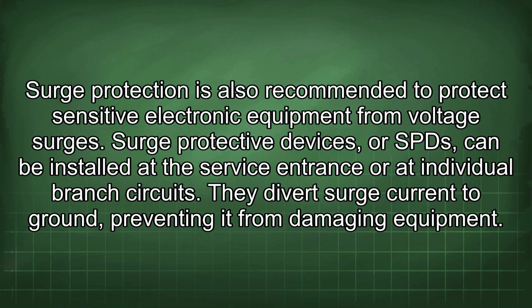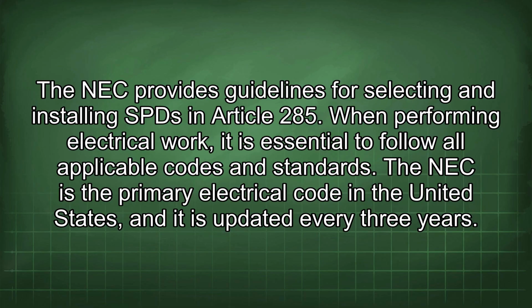Surge protection is also recommended to protect sensitive electronic equipment from voltage surges. Surge protective devices, or SPDs, can be installed at the service entrance or at individual branch circuits. They divert surge current to ground, preventing it from damaging equipment. The NEC provides guidelines for selecting and installing SPDs in Article 285.